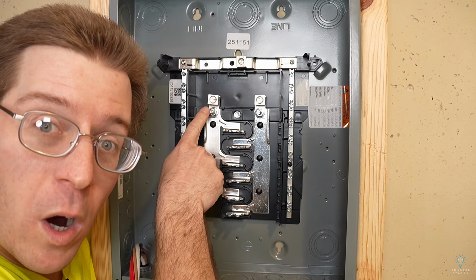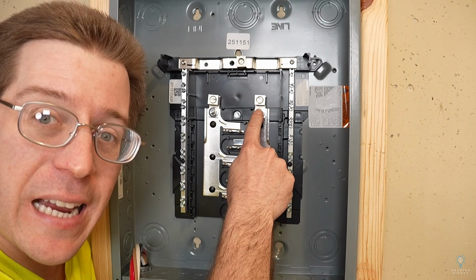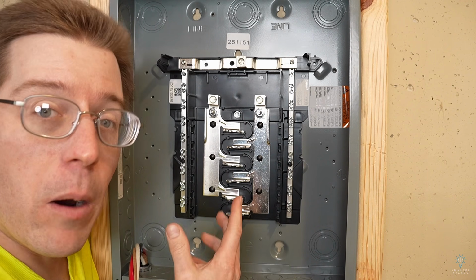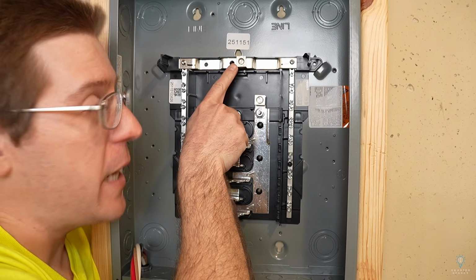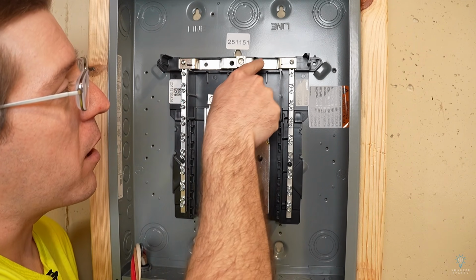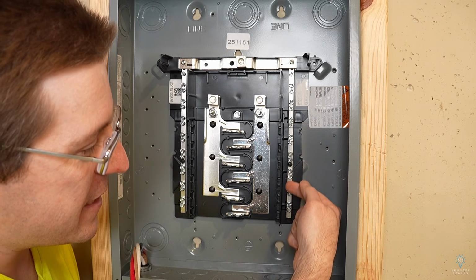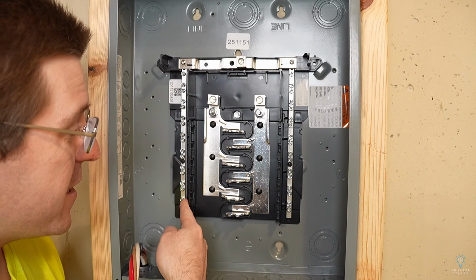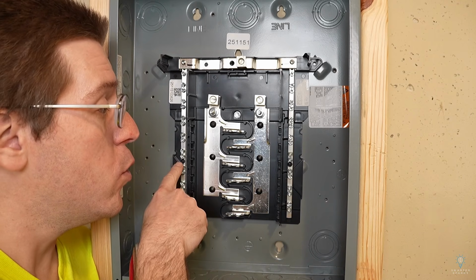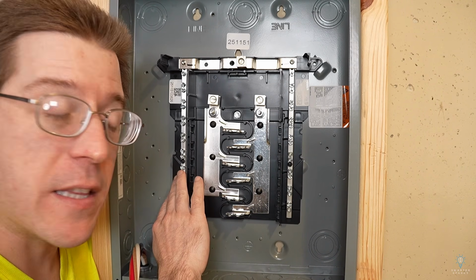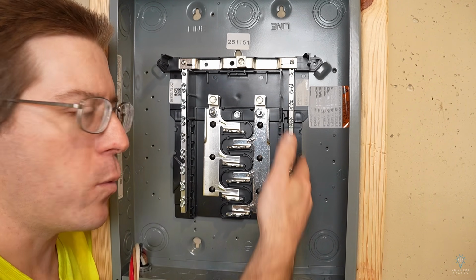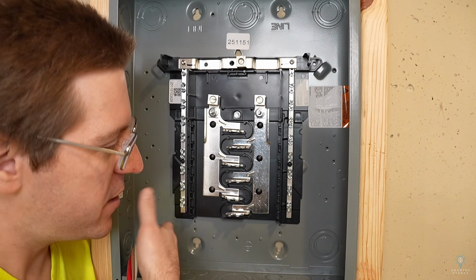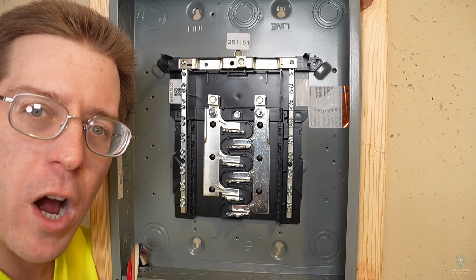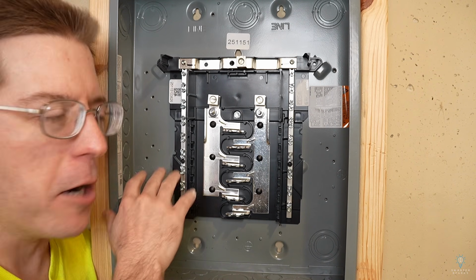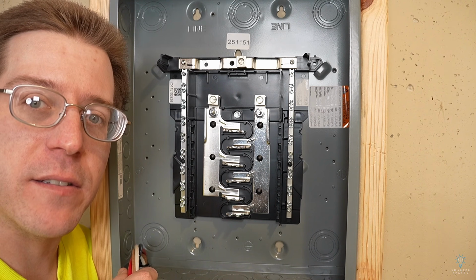So our line 1 is going to land over here and our line 2 is going to land over here. Our neutral is going to land on this terminal right here, which if we follow that bus bar straight across, it actually connects to this bus bar and this bus bar. So we've actually got two spots that we can land our neutrals in this panel. One on the left side, one on the right side. That just makes it easier so we don't have to have wires coming across if we've got a circuit over here. That's actually a pretty nice little feature of panels like this.